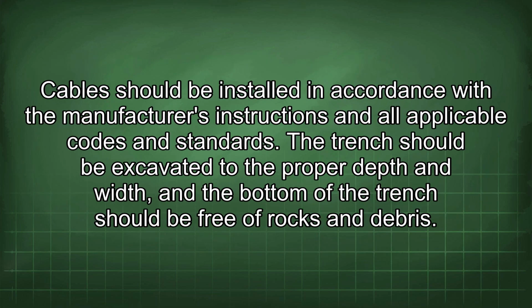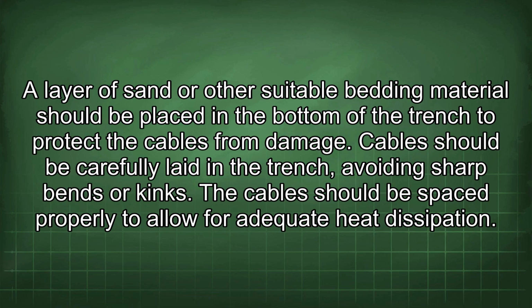Cables should be installed in accordance with the manufacturer's instructions and all applicable codes and standards. The trench should be excavated to the proper depth and width, and the bottom of the trench should be free of rocks and debris. A layer of sand or other suitable bedding material should be placed in the bottom of the trench to protect the cables from damage. Cables should be carefully laid in the trench, avoiding sharp bends or kinks. The cables should be spaced properly to allow for adequate heat dissipation.